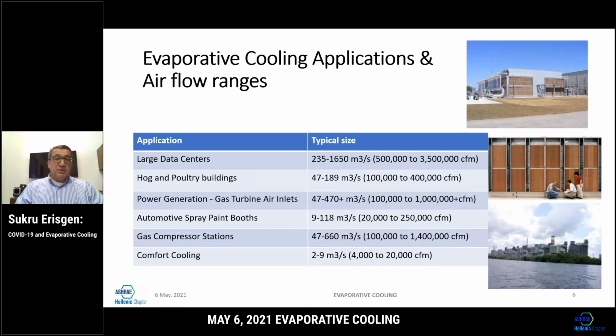As I mentioned, for evaporative cooling applications, the airflow ranges can be very large, from small comfort cooling, 2 to 9 cubic meters per second, all the way to large data centers or power plants. Airflow capacities can go up to 1,650 cubic meters per second. This is very large. This can be achieved by what we call evaporative cooling banks, and they can be stacked side by side or on top of each other.